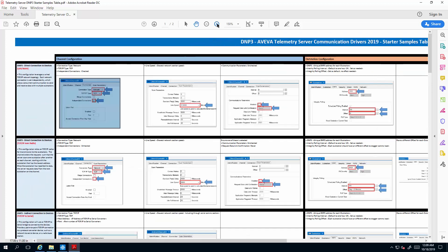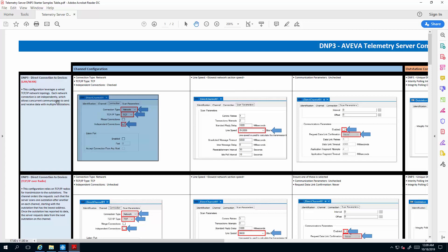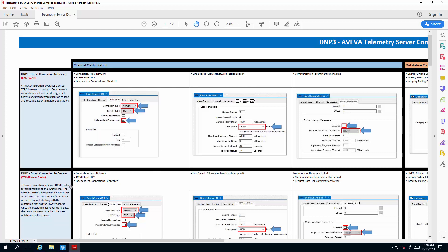If we zoom a little bit in the table, you will notice that for each one of them, we depict what are the typical settings that you would use. Now, keep in mind that the settings here are sample settings. They're typical, but you have to pay attention to your specific configuration. As I mentioned before, if I'm using a wired connection in my network, I will pick independent connections. If I'm using TCP over radio, I will use dependent connections, so I wouldn't check that box. Similarly, in a wired connection, you're going to have greater network speed. Your bandwidth would be higher. If you're using radio equipment, you have to actually match the capability of the radio, so you will pick a bandwidth that applies to your radio.